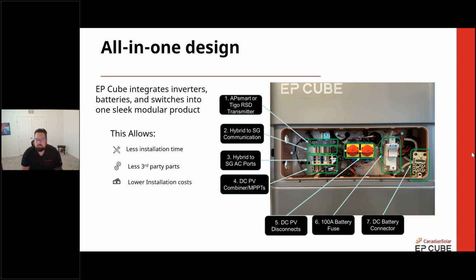As you can see with the actual ports, they don't come quite like that. They have screw-in ports, so you can use 3/4 and thread it directly in. I wouldn't though. I typically go up to 1 inch, it just makes it a lot easier. I'm not a big fan of pulling wires as a former residential electrician, so if I can avoid pulling wires through conduit, I try to. Bigger conduit is always better for me, so that's usually what I do.